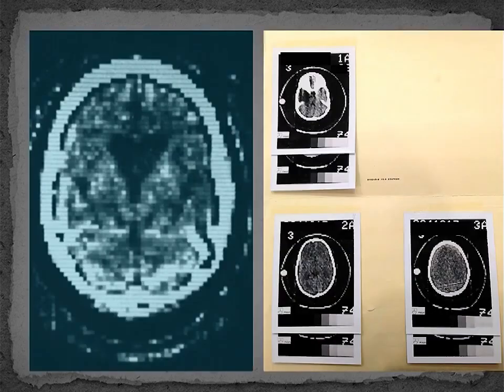The images from the system were captured using Polaroid film, and an entire CT exam consisted of six such Polaroid images. This scanner was actually the first multi-detector CT system, as it acquired two line integrals at each position of the detector and gantry using two different sodium iodide detectors.